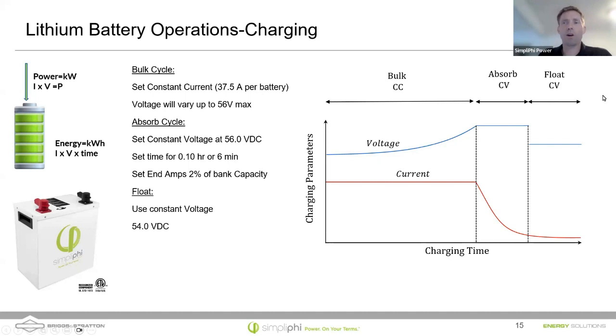There's a third part of the cycle, also constant voltage, called float. Normally we don't recommend using float - it just keeps the batteries at 100% state of charge. We only recommend floating the batteries if you have a free energy source, like extra solar coming in that's not being used, and you want to keep your batteries 100% topped off - you can float the batteries at 54 volts.